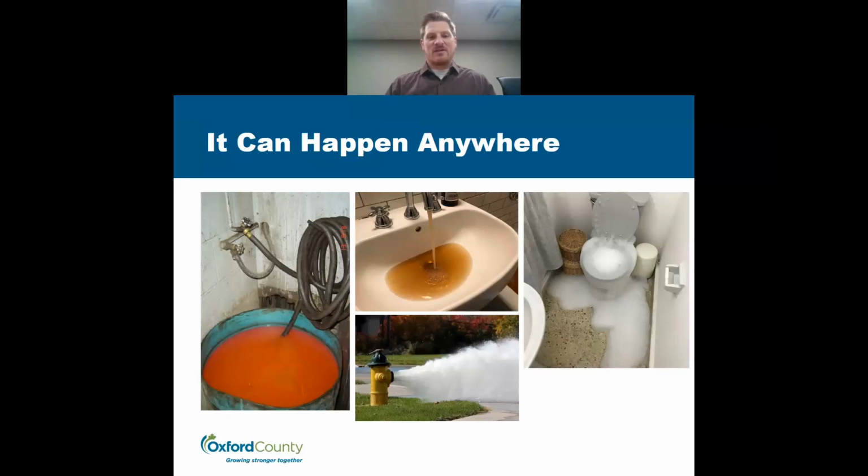It can happen anywhere. Something like a hydrant blow-off releasing a large amount of water can induce a back siphonage event, and then something as simple as a hose draped into a barrel of chemicals can siphon water into the municipal drinking water system, which can then be distributed through taps, or in the case of foaming agents, can come up through residences, toilets, or other fixtures.